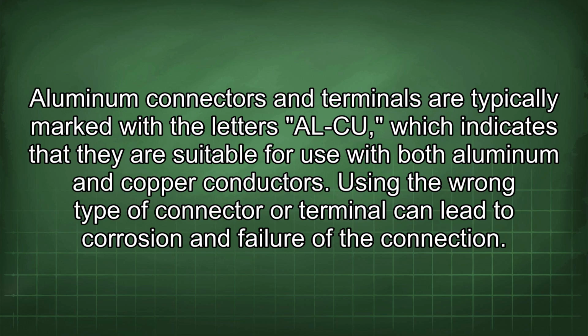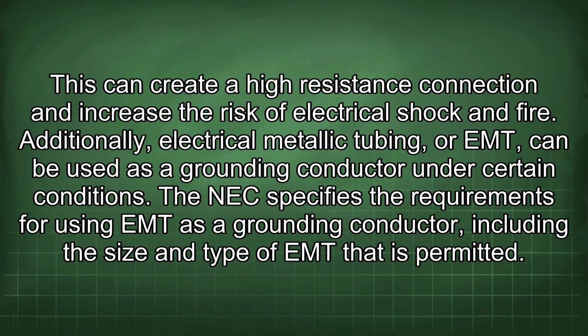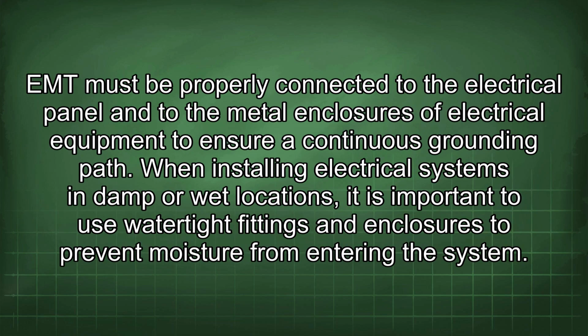Using the wrong type of connector or terminal can lead to corrosion and failure of the connection. This can create a high-resistance connection and increase the risk of electrical shock and fire. Additionally, electrical metallic tubing, or EMT, can be used as a grounding conductor under certain conditions. The NEC specifies the requirements for using EMT as a grounding conductor, including the size and type of EMT that is permitted. EMT must be properly connected to the electrical panel and to the metal enclosures of electrical equipment to ensure a continuous grounding path.